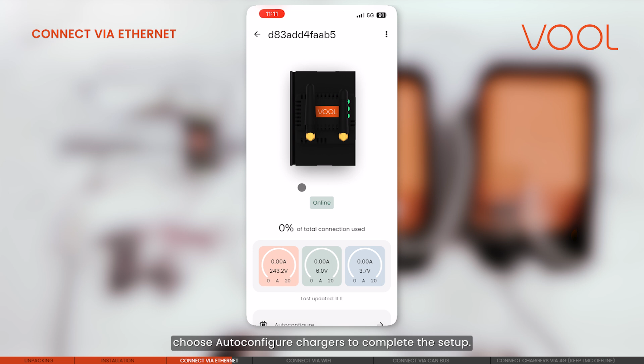Finally, in the LMC settings, choose Auto-configure chargers to complete the setup. Make sure to insert the correct grid connection size in the LMC settings, and set the charger current limit according to the charger circuit breaker size in the charger settings.